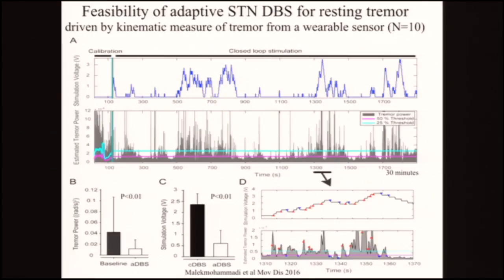And if it goes below this threshold, the stimulator will start decreasing. We had to do an awful lot of preparatory work determining the safest ramp-up speed of the voltage for the patient and the ramp-down speed, and found, in fact, that if we ramped down too quickly, we almost had a recurrence, a rebound of tremor. So we ramped up at the fastest speed that the patient could tolerate so that we could grab that tremor and get rid of it. And then we ramped down at half the speed.